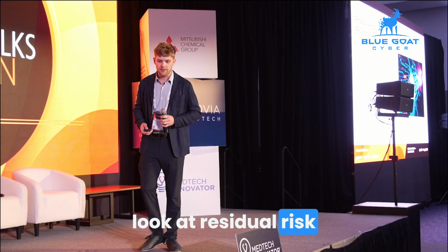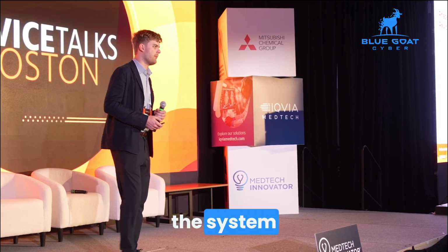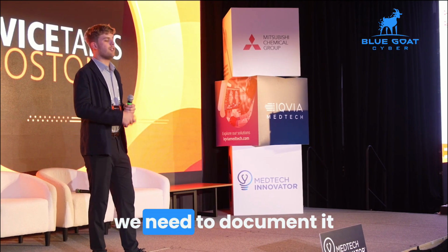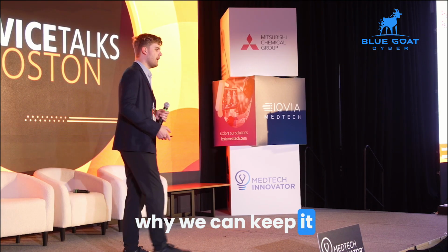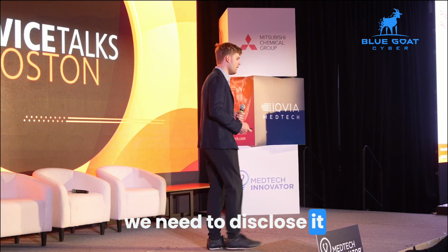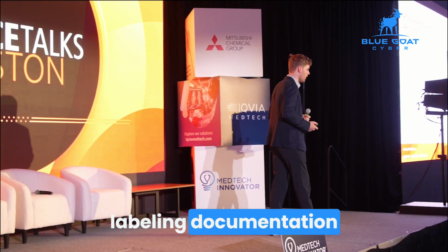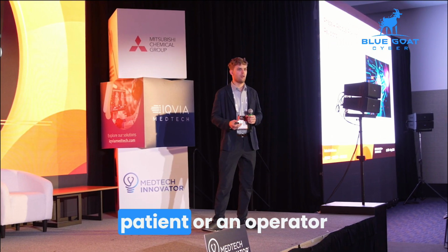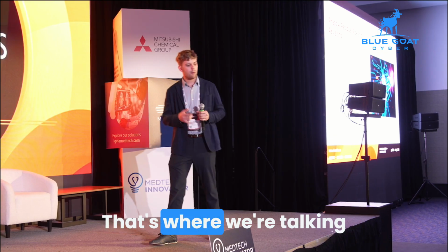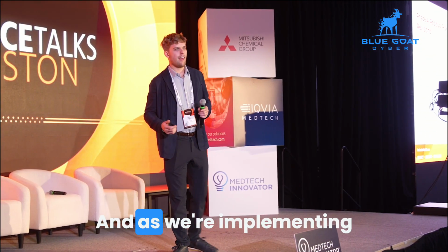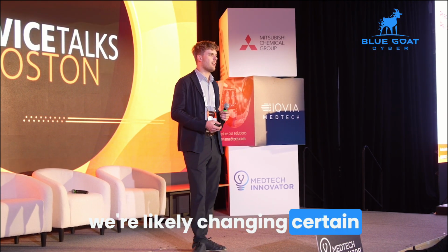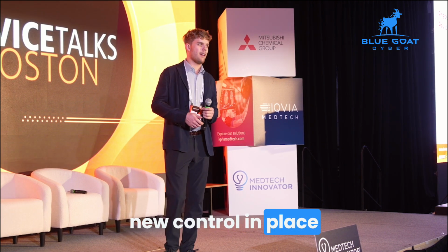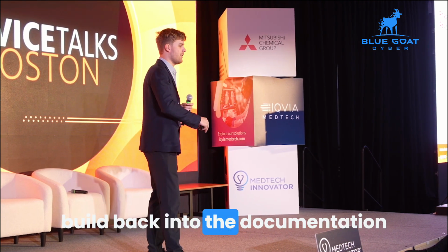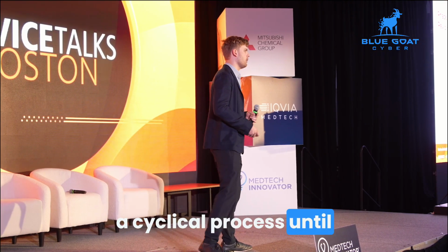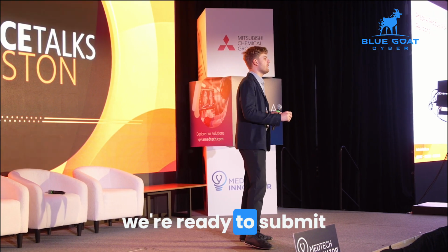Now we need to look at residual risk. So we talked about what can make a risk acceptable, when can we have a risk still in the system. Once we've identified these risks, we need to document it, we need to explain why we can keep it, and then importantly, we need to disclose it. So when we're preparing labeling documentation, we need to state any risk that a patient or an operator could be exposed to in the system. That's where we're talking about this residual risk. And as we're implementing these controls, we're likely changing certain aspects of the device. We may have a new control in place that wasn't there before that we need to build back into the documentation. So it can be a cyclical process until we get to a final good mark where we're ready to submit to the FDA.